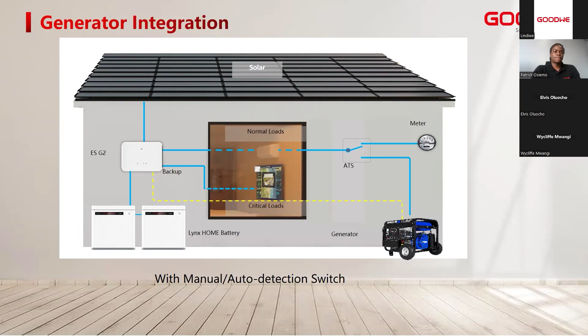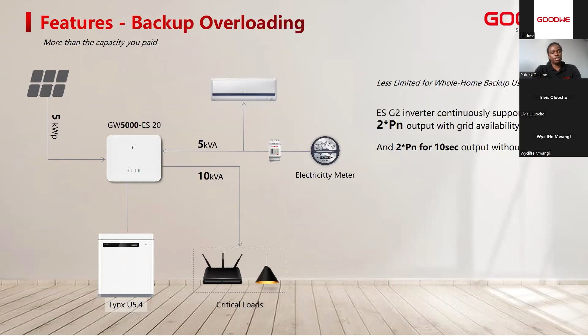In terms of backup overload, and yes, I did mention this before in the ESG2 datasheets, the inverter can give a maximum of 10 kVA or 10 kilowatt continuously when grid is available. In this sense, you can get 5 kVA from the grid and a surplus 5 kVA from the PV system or the battery itself, giving you a total of 10 kVA output from the inverter. And once the grid fails, the inverter does support a maximum of 10 kVA power draw from the battery backup itself, but then you will be limited to a maximum of 10 seconds. 10 seconds is actually a very wide window. This gives time for your inrush loads to switch on and go back to their normal operating power. And in this sense, your hybrid installation is not interrupted with generation. It continues producing seamlessly.